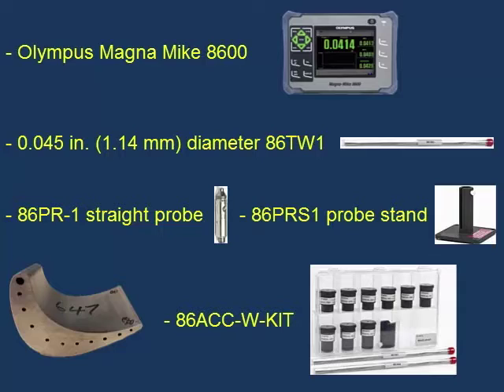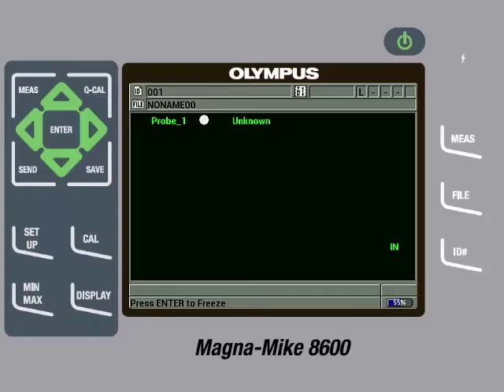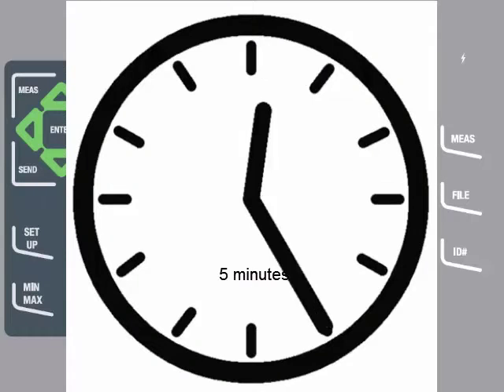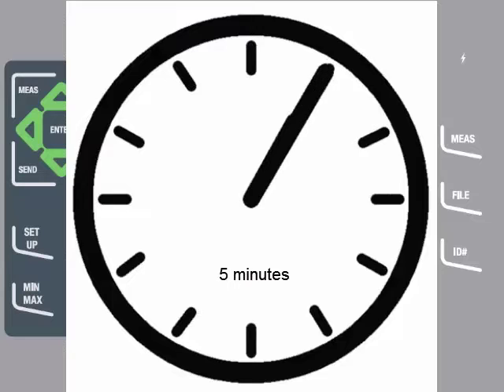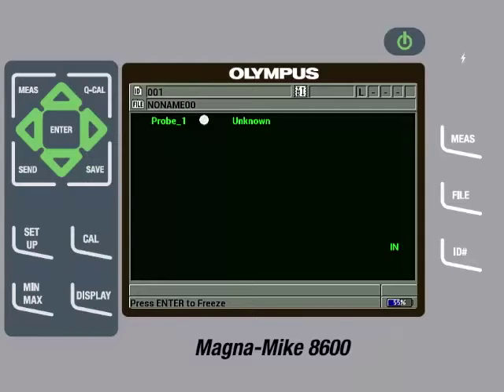The first step would be to connect the probe and probe cable to the instrument and then turn the instrument on. It is important to let the instrument warm up for at least 5 minutes before using it so the probe can reach a steady-state temperature condition. The Magna-Mike 8600 can auto-detect the different size target balls, but it cannot auto-detect the wire or disc targets. Therefore, we will need to tell the instrument what target we are going to use.